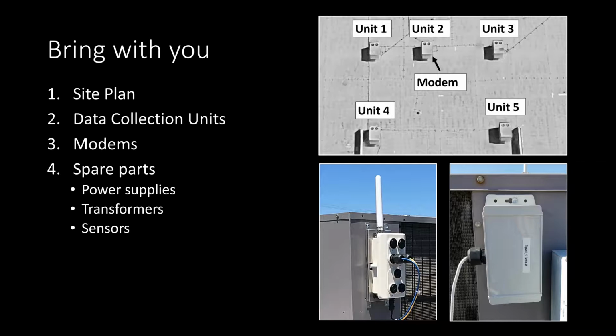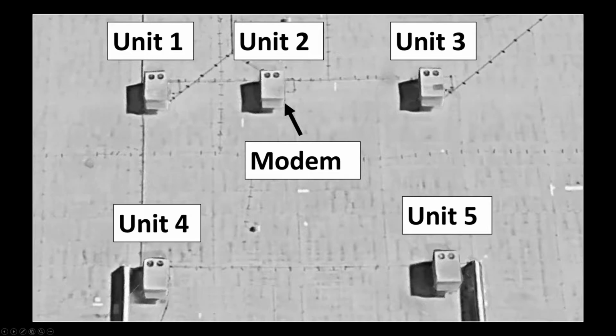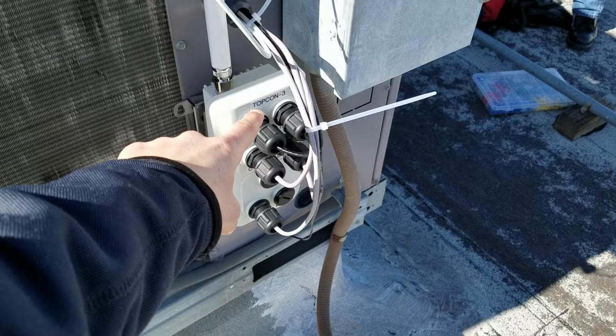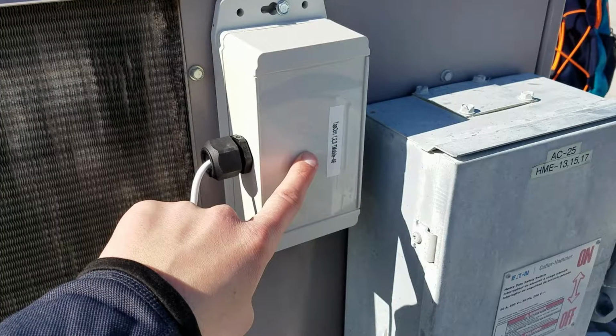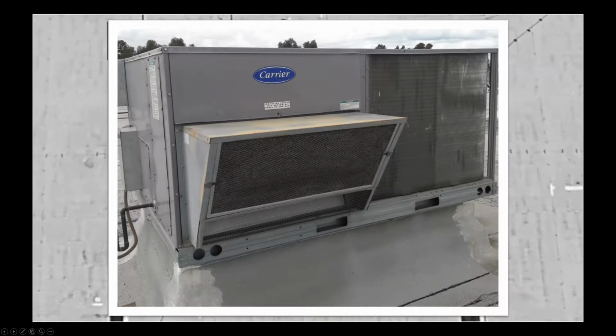When you arrive on site, gather all equipment, a spare parts kit, and the tools required to perform the installation. Contact the facility supervisor and proceed to the HVAC units which are indicated on the site plan. First, go to the unit on which both the DCU and modem will be mounted. This should be near the center of the group of units. Then find the modem and the DCU for the unit and double check that the DCU serial number matches the one on the plan. Lastly, walk around the unit and note any potential options for mounting both the DCU and the modem on the exterior of the HVAC unit.